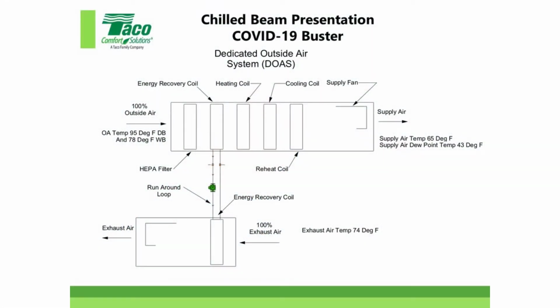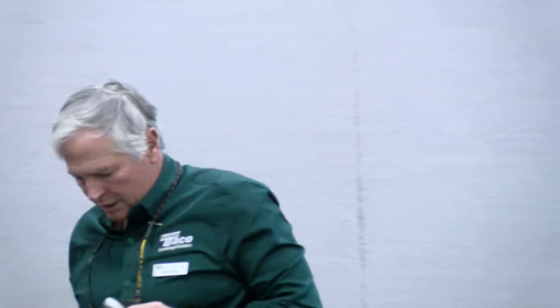This is the dedicated outside air unit, the energy recovery unit, whatever you want to call it. It's very important. You need to design the air that gets to those chilled beams to be very dry. Here's the exhaust air coming out of the zone, and that goes out here. But the wet air, maybe not in Vegas, it's pretty dry out there, but for Miami, Houston, places like that, even Rhode Island, this wet air comes in here. It has to go through a filter, and also through a recovery and a heating coil to get the dew point out, and then be cooled back down before it goes into the room. So it's going into the room very dry, around a 43 degree dew point. There's a little difference in working with the DOA unit, but you do have to take that into account when you design it.